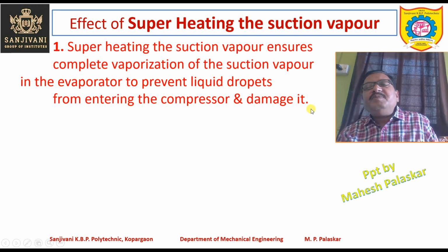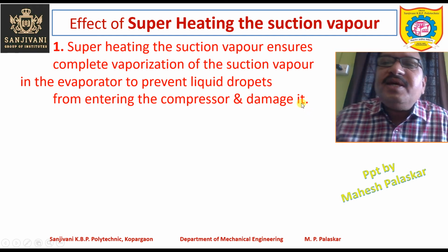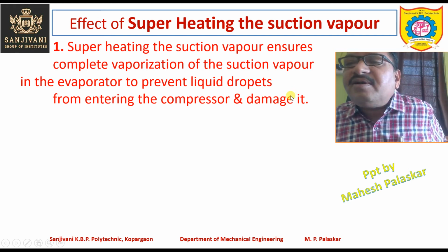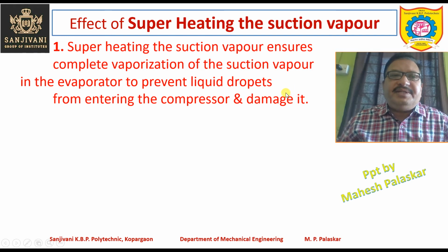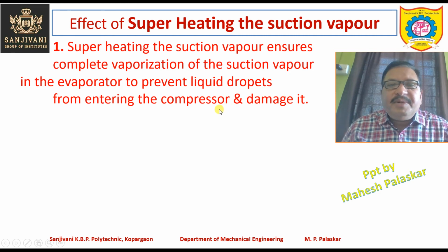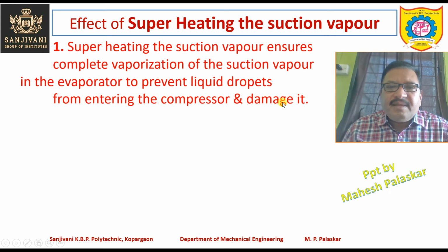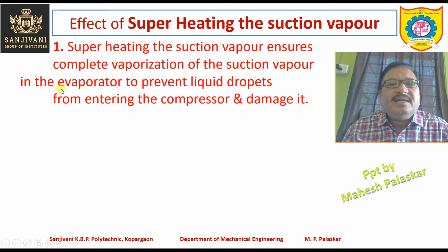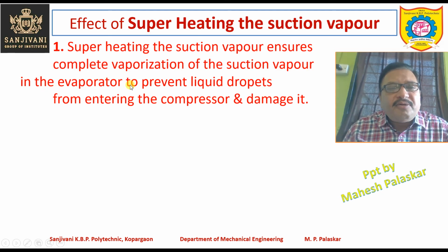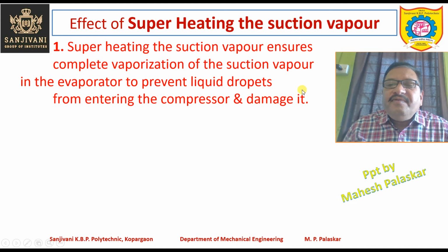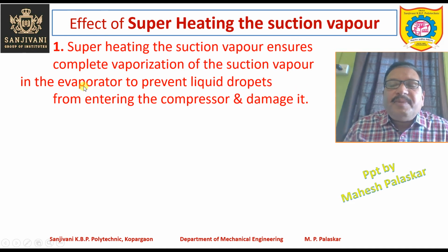So the main purpose of superheating is not to increase the COP or increase the refrigerating effect. That is not the main purpose of superheating. The main purpose of superheating is to increase the life of the compressor, because superheating ensures the complete vaporization of the suction vapor in the evaporator or outside the evaporator to prevent liquid droplets from entering the compressor and damaging it.